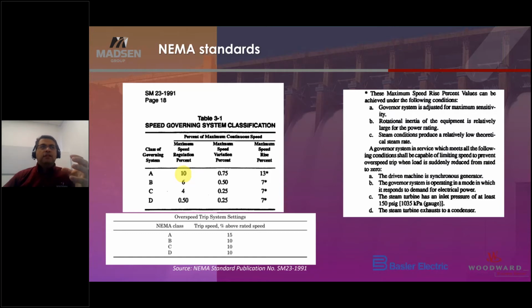If you imagine that this is the error in the speed changes, for a mechanical governor it's around 10%. For an electrical governor, or what we call NEMA D, most of the electronic governors, like the one that we talked about, the 5000 and H, are within 0.5%. So this is the percentage error that is accepted from your rated speed. And then the maximum rise: we define it as what happens when you lose the load. So for an unknown reason, you were at 100% of the load, and then you lost the load. How much speed rise would be accepted by NEMA A? You can get up to 13% if you have a NEMA A governor, but with an electrical governor, it is acceptable up to 7%.